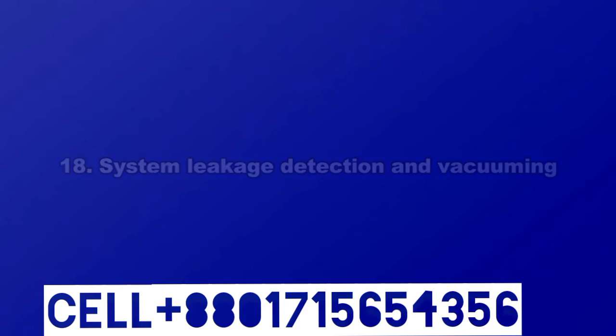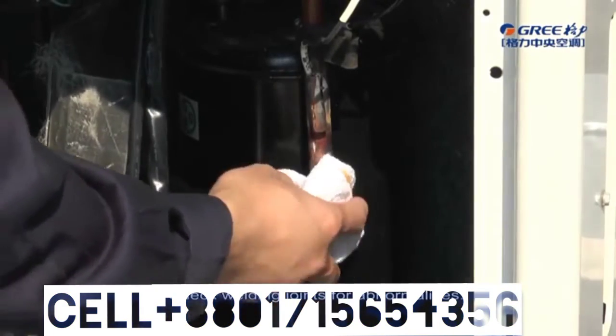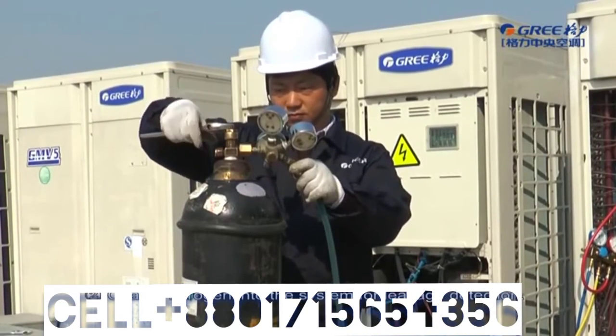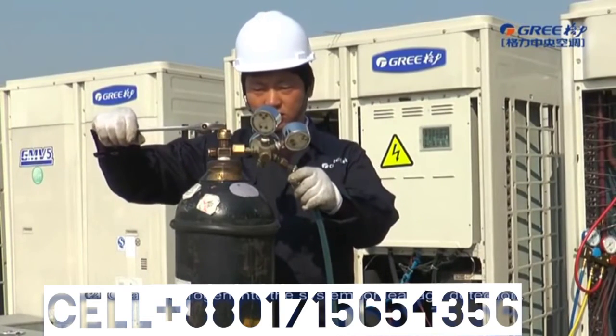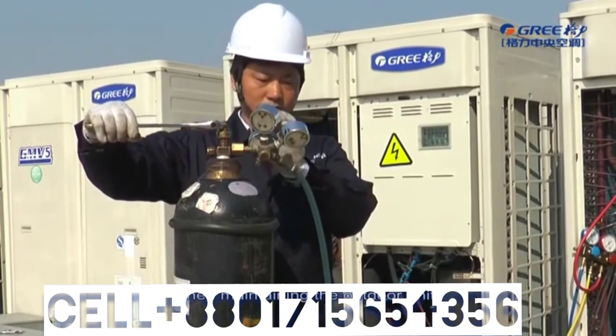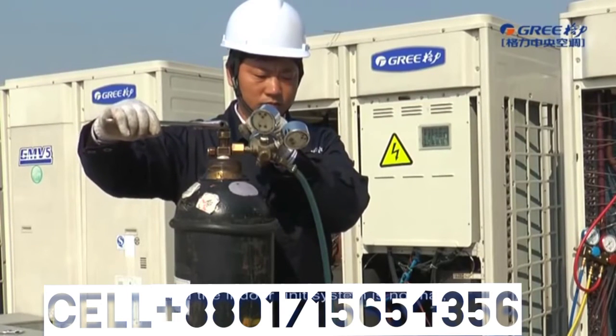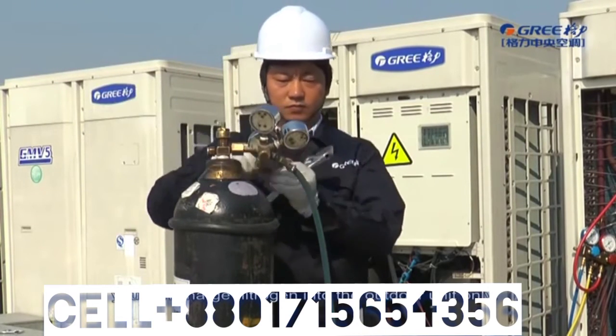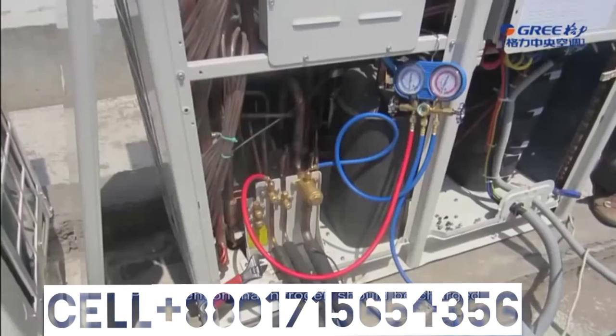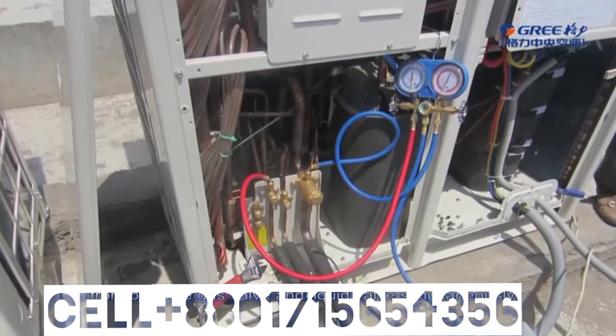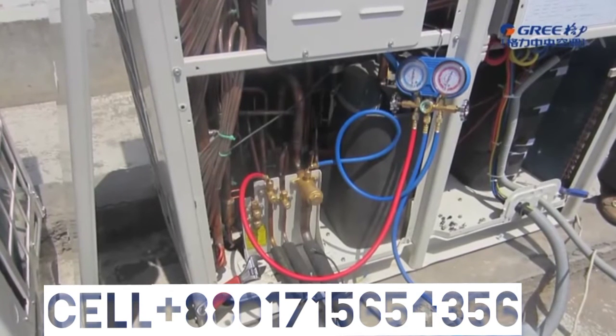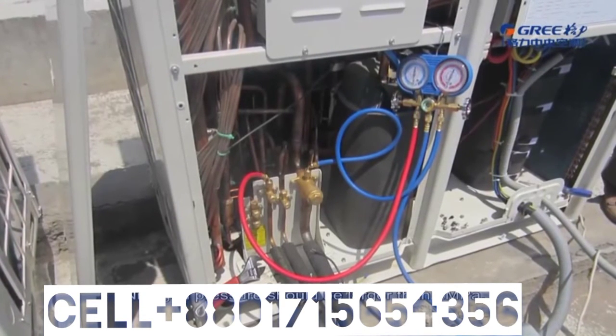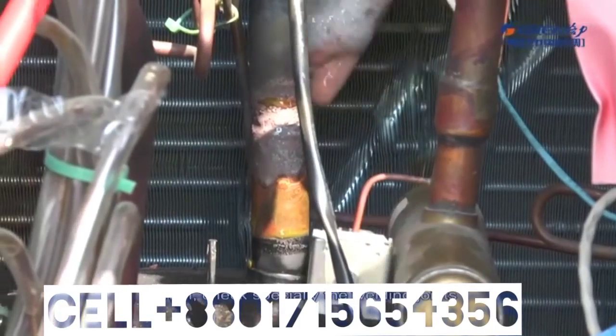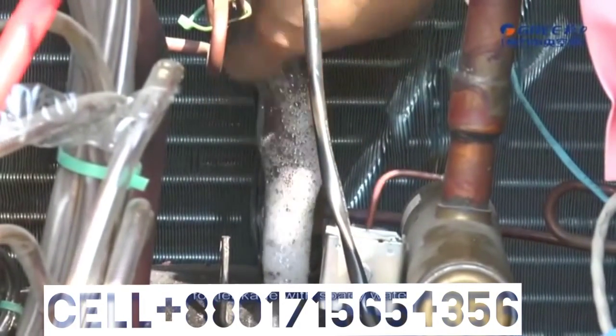18. System leakage detection and vacuuming. First, check welding joints for abnormalities. Second, charge nitrogen into the system for leakage detection. When maintaining the outdoor unit and the indoor unit system is normal, you can charge nitrogen into the outdoor unit only. Pay attention that nitrogen should be charged from both the gas valve and liquid valve simultaneously. Nitrogen pressure should be larger than 2 megapascals. Then, check specially the welding joints for leakage with soapy water.